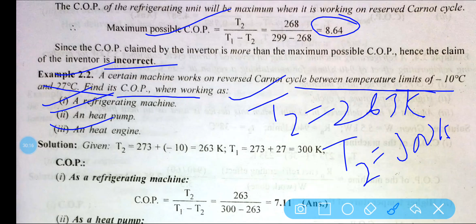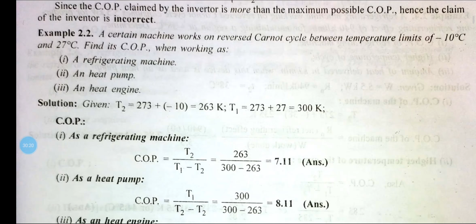Now what do you need to find out? The COP when it is working as a refrigerating machine. In case of a refrigerating machine, the COP should be T2 by T1 minus T2, so 7.11 is the answer. But in case of a heat pump, it should be T1 by T1 minus T2, so it is 8.11. Or you can easily write that the COP of the heat pump is the COP of the refrigerating machine plus 1. That means if you add 1, you will get the COP of the heat pump, because we know that COP of a heat pump is equal to 1 plus COP of the refrigerating machine.